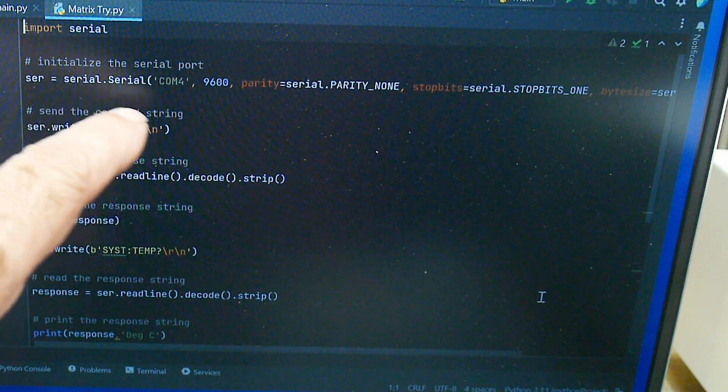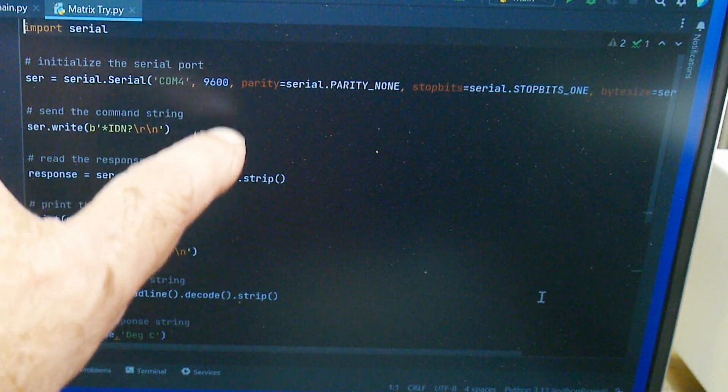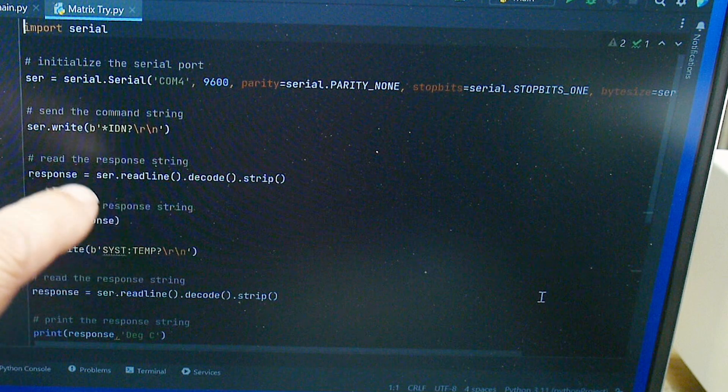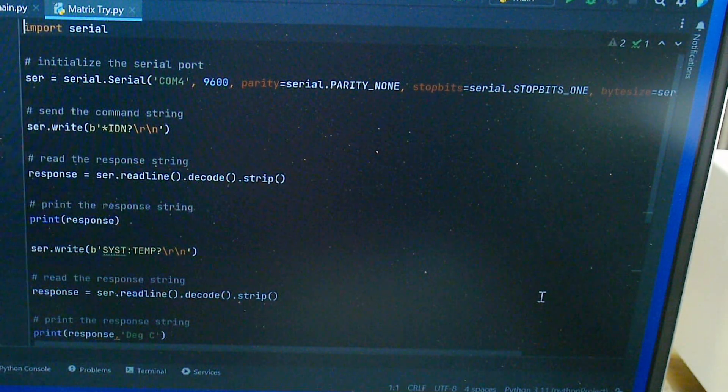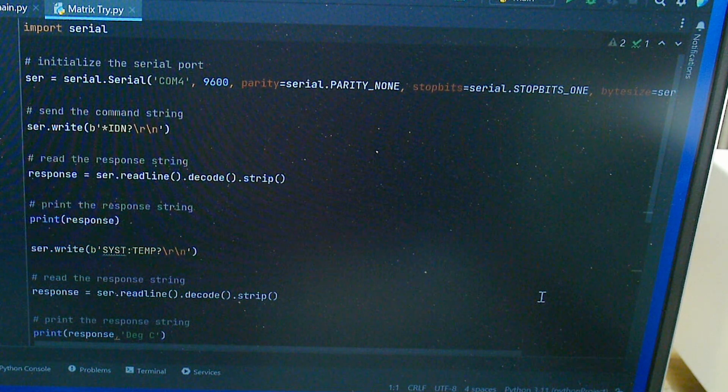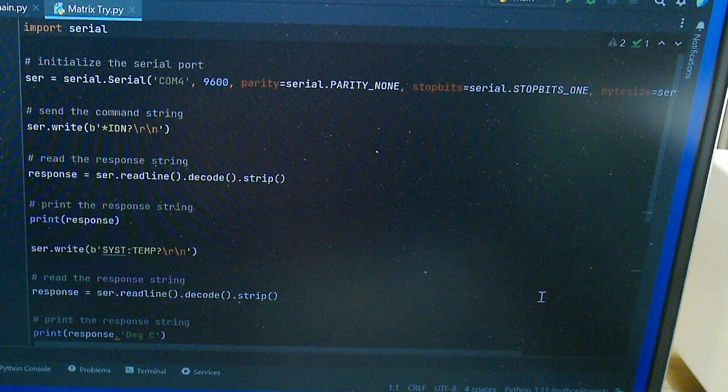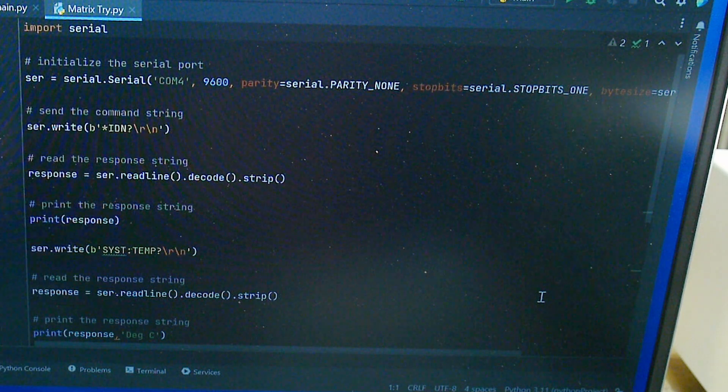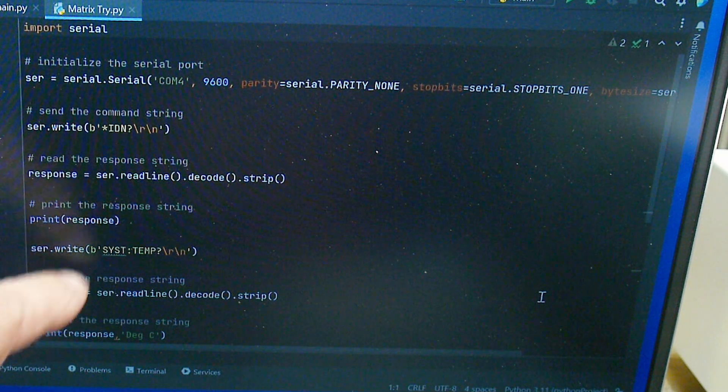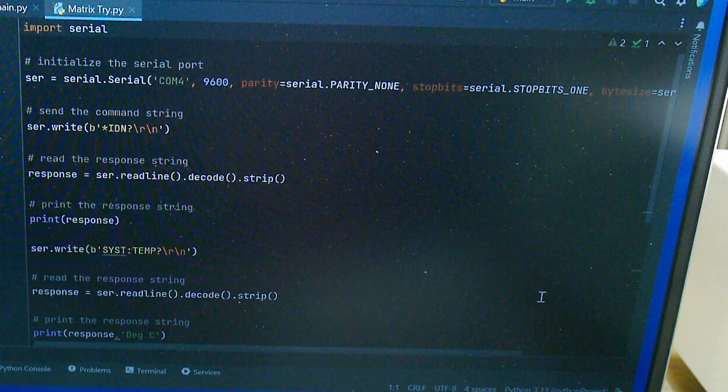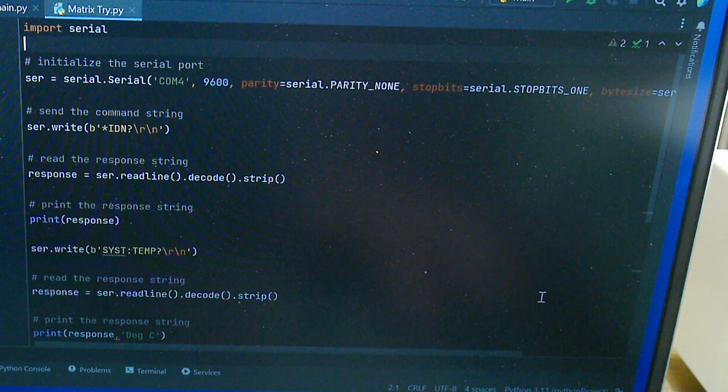You set the serial port, say serial is COM4, 9600, and you can set all the stop bits and stuff. Then I'm going to issue the command star IDN question mark, carriage return, line feed. I have the machine set up for that. Then we're going to send it, we're going to read from it, see if it identifies itself. Next thing I want to do is send it a command which was system temperature question mark, so it has a way of measuring its own internal temperature and we will execute that.